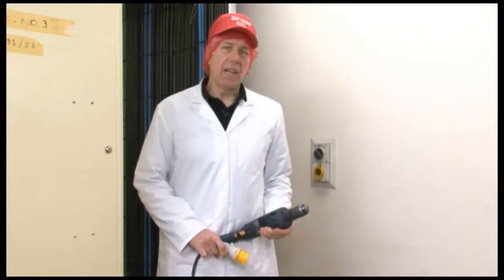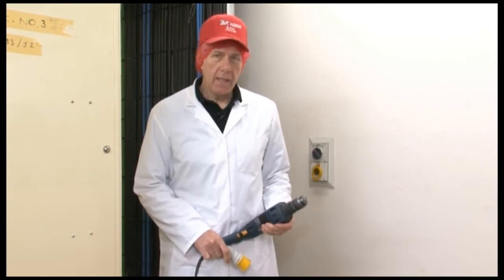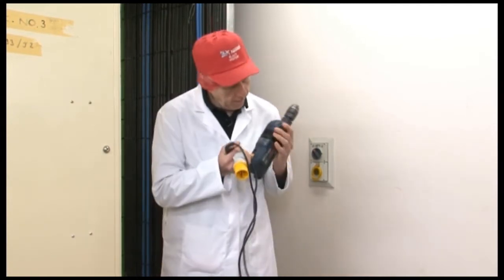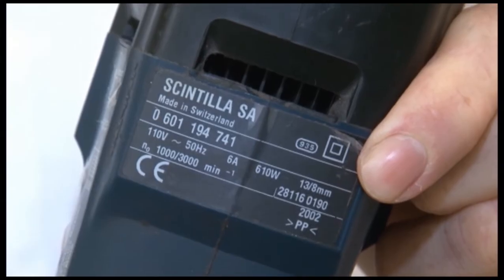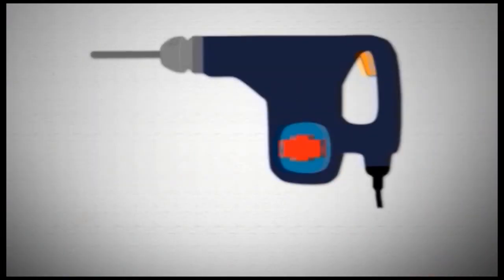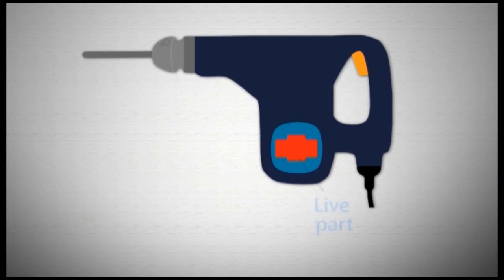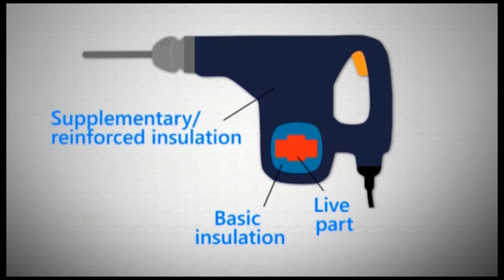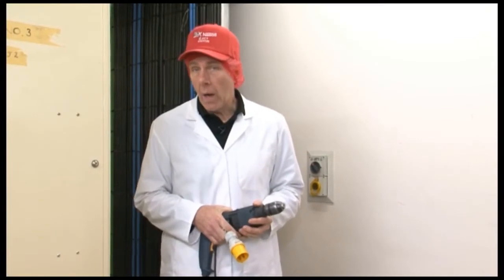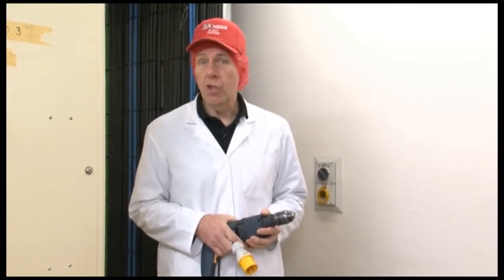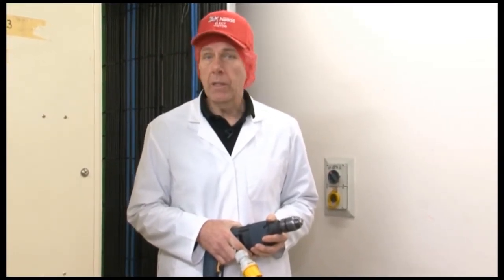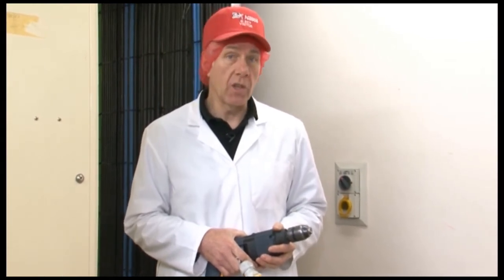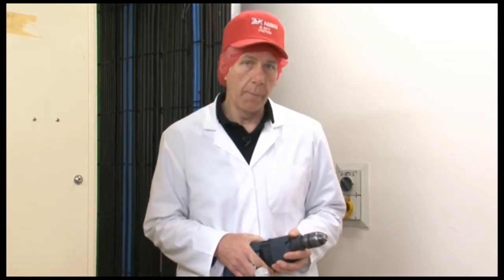Another very common technique for complying with Regulation 8 is double insulation. The symbol shown here indicates that the equipment is double insulated. The principle of double insulation is that any live conductors of the electrical equipment are covered with two distinct layers of insulation, each of which would adequately insulate the conductor. So if one layer failed, the other would be sufficient to protect the user, and the probability of danger arising before damage to the insulation is spotted is extremely low.